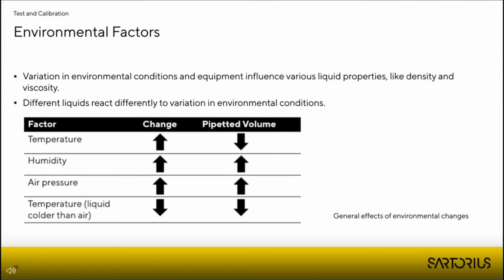As already said, the environmental conditions under Part 6 and 8 are very strict. The reason behind this is that variations in the environmental conditions have an influence on the test and calibration results. The table shows general effects of environmental changes with distilled water and how this affects the dispensed volume. Looking first at the air temperature: when the air temperature increases, the airspace between the seal and the liquid, as well as mechanical parts, expand a little bit. As a consequence, the pipetted volume will be a little bit less.